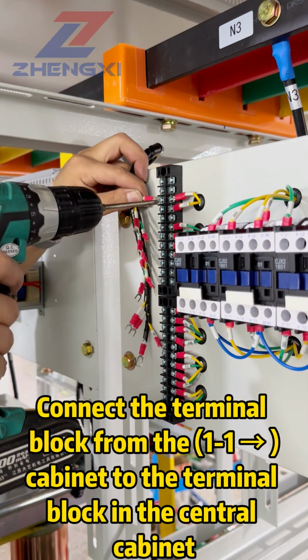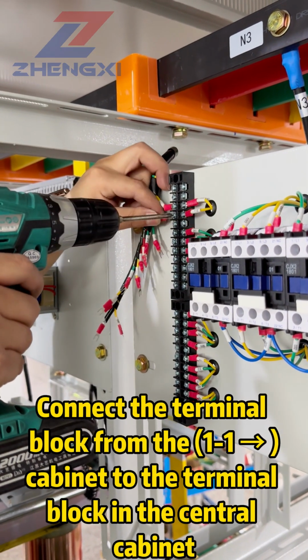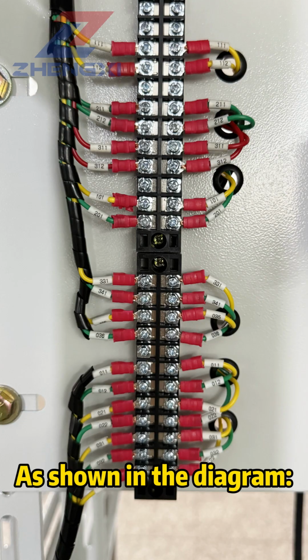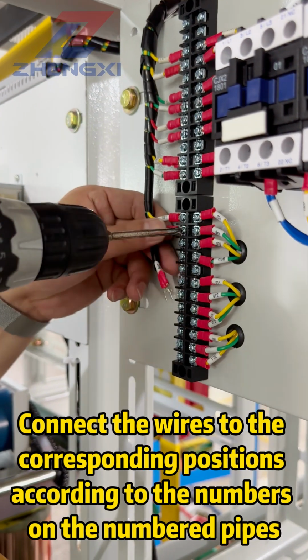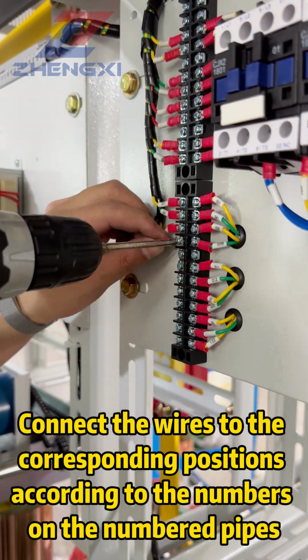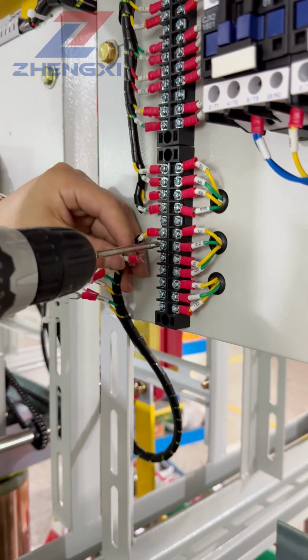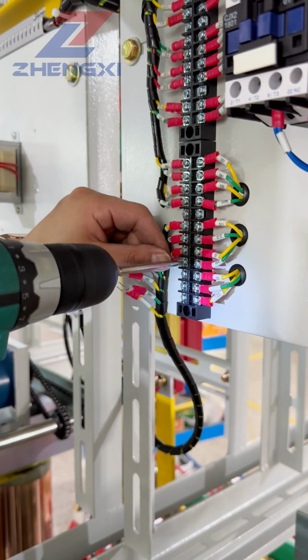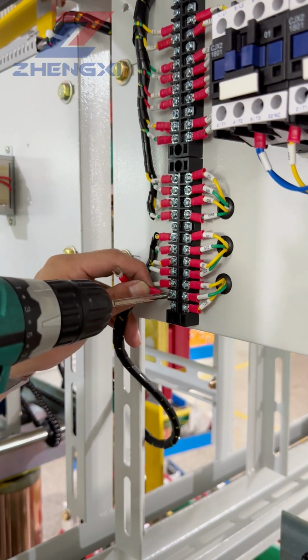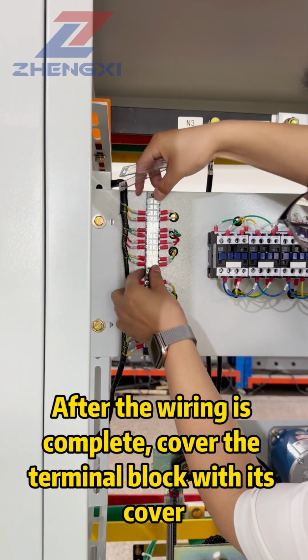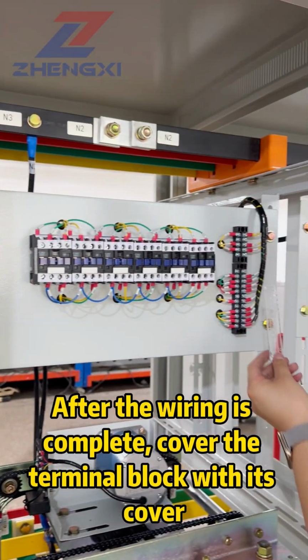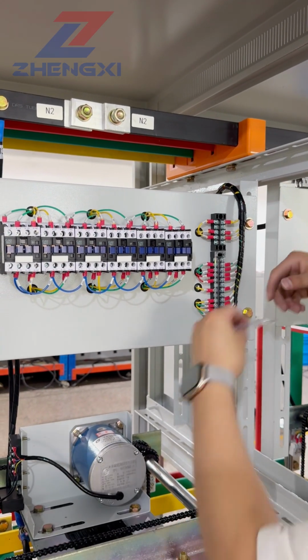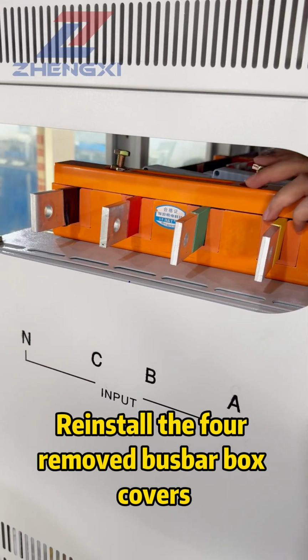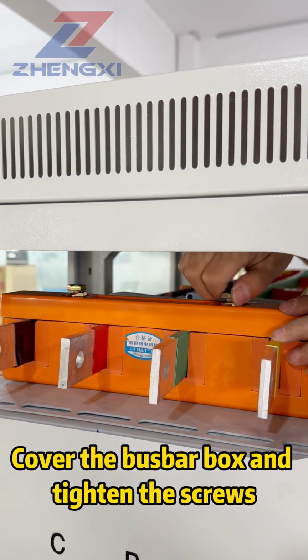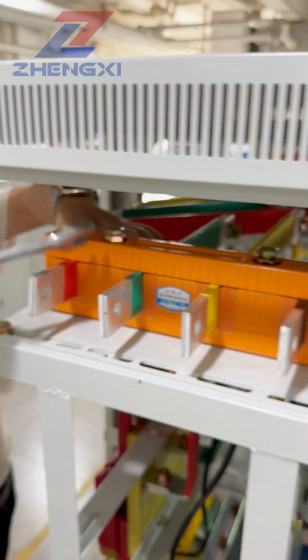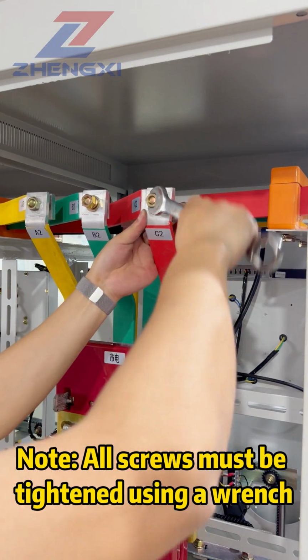Connect the terminal block from the 1 and 1 cabinet to the terminal block in the central cabinet. As shown in the diagram, connect the wires to the corresponding positions according to the numbers on the numbered pipes. After the wiring is complete, cover the terminal block with its cover. Reinstall the 4 removed busbar box covers. Cover the busbar box and tighten the screws. Note: all screws must be tightened using a wrench.